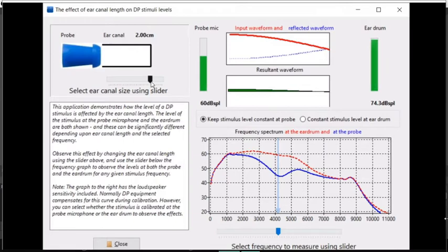And we do it by trying to identify what looks rather like a resonance notch, and therefore drawing a straight line over it so that we deliver what we believe is an accurate sound level at the ear canal. But that begins to get problematic at certain frequencies once the ear canal gets to a certain length, and there's no defined age when it becomes problematic, because it depends upon how far the probe is inserted into the ear canal and how long the ear canal is, and obviously that varies from person to person.